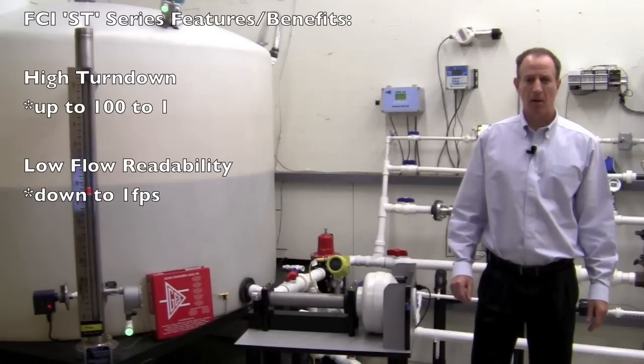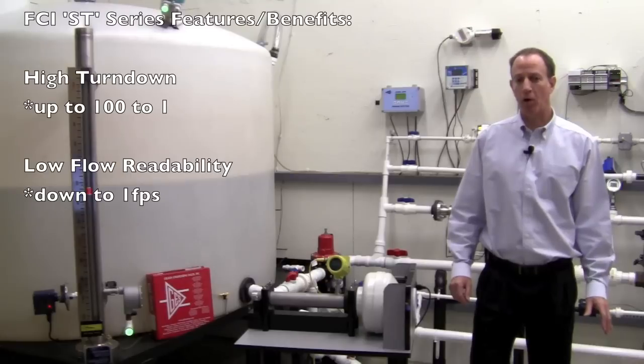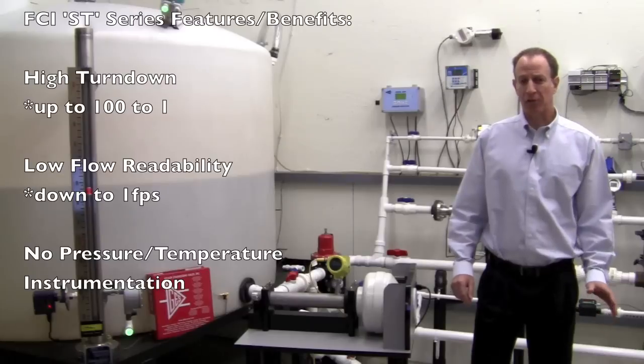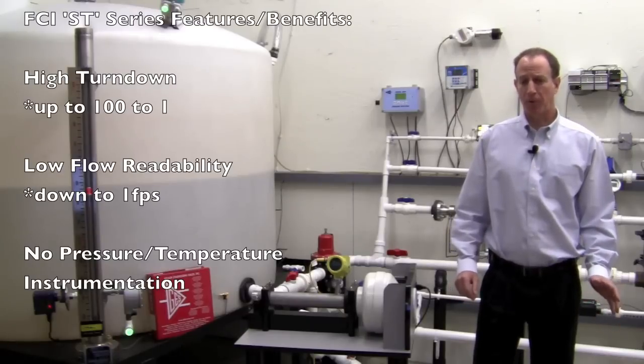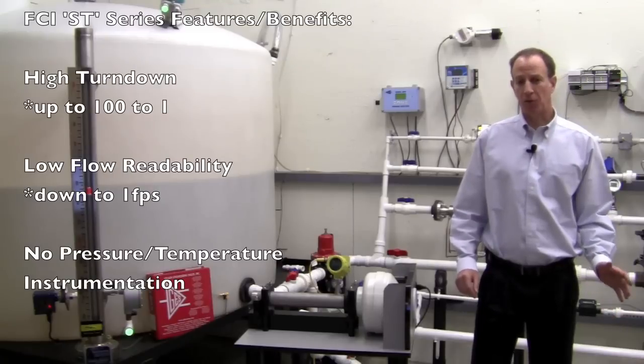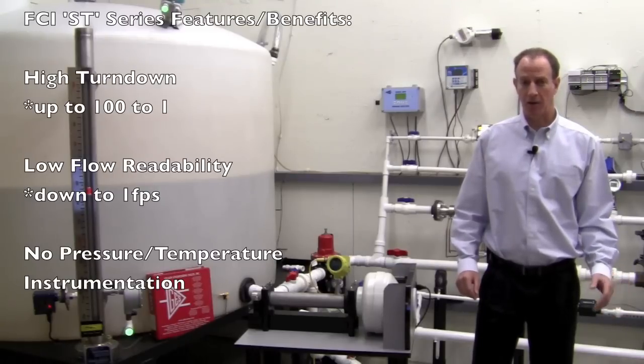Low flow capability. The gas flow sensor can measure down to one foot per second. No pressure or temperature compensation required. To get true mass flow, differential pressure and vortex flow meters require pressure and temperature compensation. This increases both hardware and installation costs.